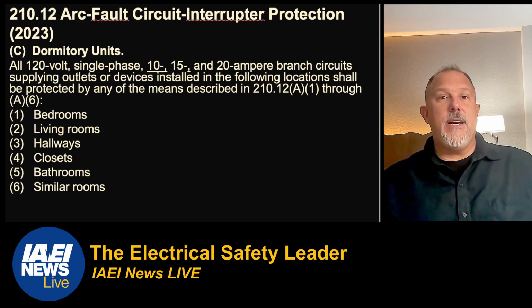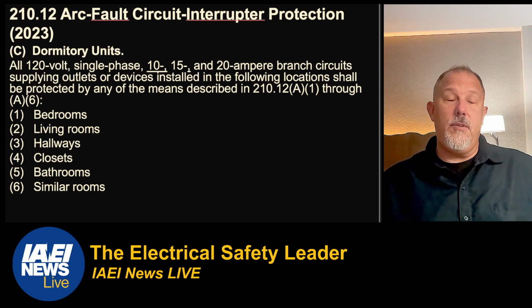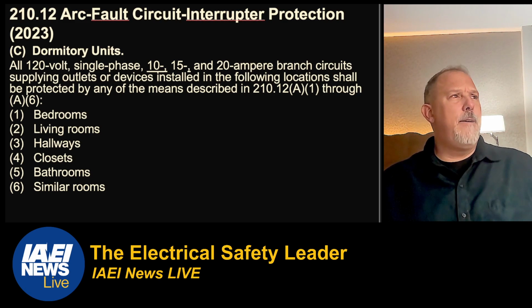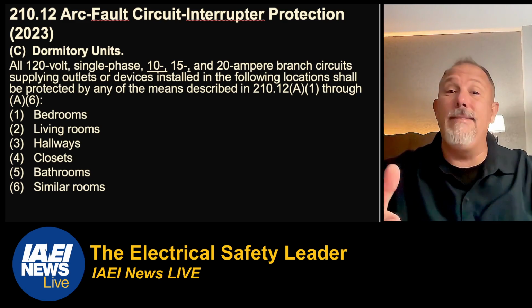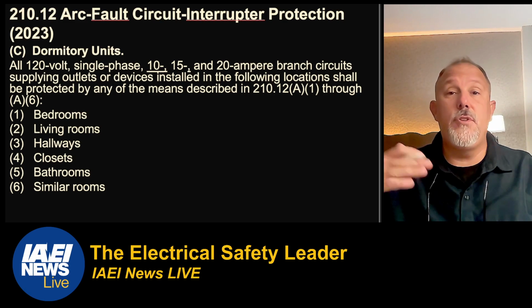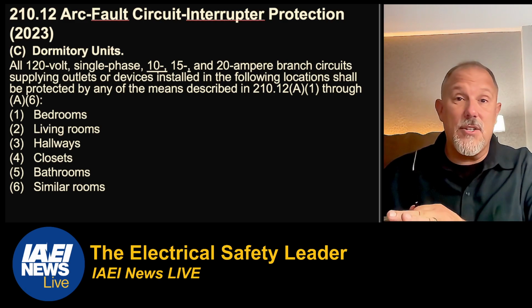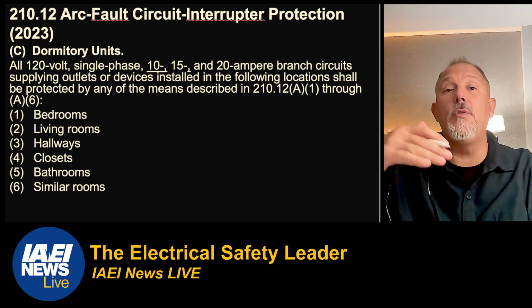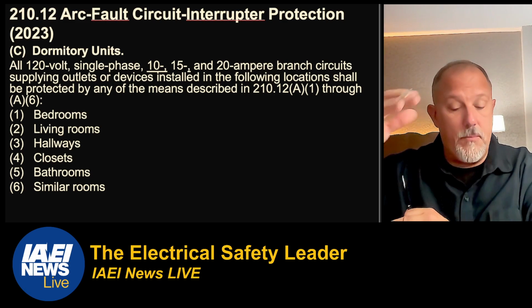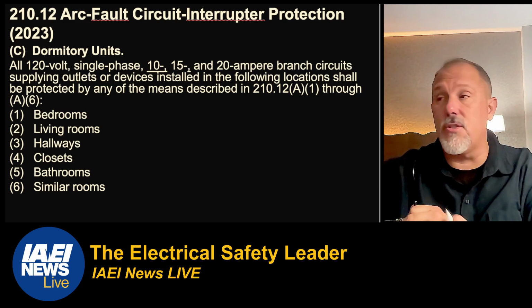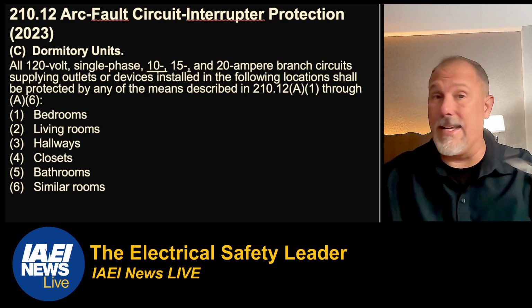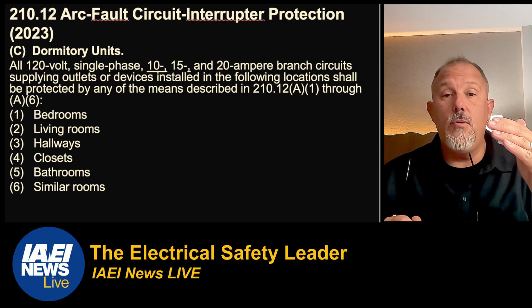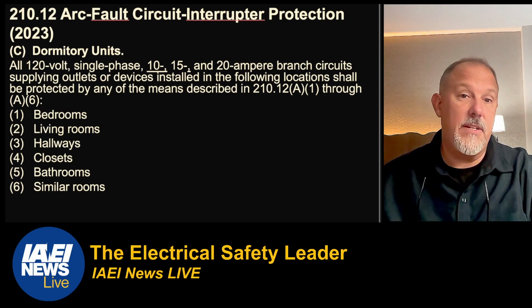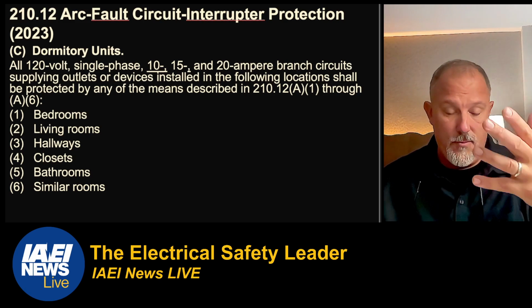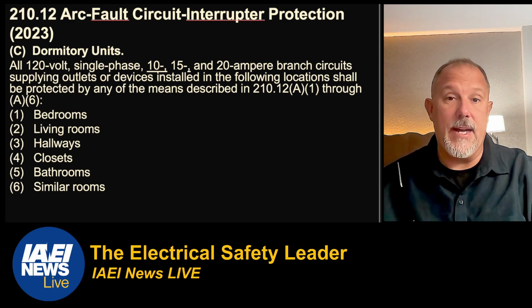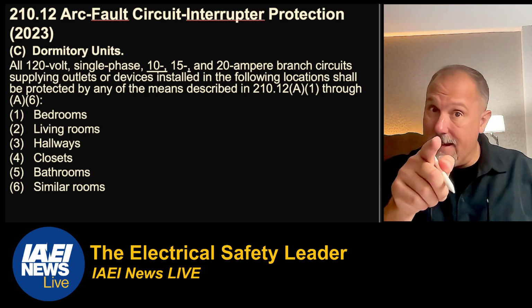So you have 10, 15, and 20 amp branch circuits. Is there a 10 amp AFCI? No, just like there's no supplemental arc protection, and you probably can't find a branch feeder AFCI. But it's in there. So if you do start to see 10 amp branch circuits for lighting circuits only, remember, you've got to look at the requirements on where you can actually install a 10 amp circuit. We put some restrictions on what can be served. You can't serve a receptacle outlet on a 10 amp circuit because we don't make 10 amp receptacles. But you can do that on lighting circuits. And if it's in a residential dwelling unit in any of those rooms in A, you're going to need to have AFCI, but we don't make a 10 amp AFCI yet.